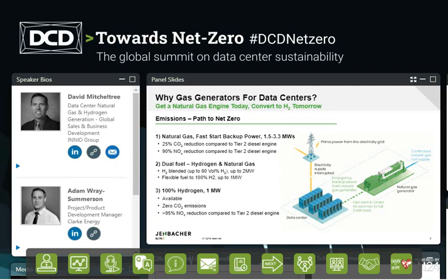Dual fuel is kind of the next iteration. We've had dual fuel engines out there - when I say dual fuel, that's hydrogen and natural gas blended up to 60%. We've got a test bed, a little 1 megawatt unit that went from 100% methane to 100% hydrogen - that was our successful test last year.